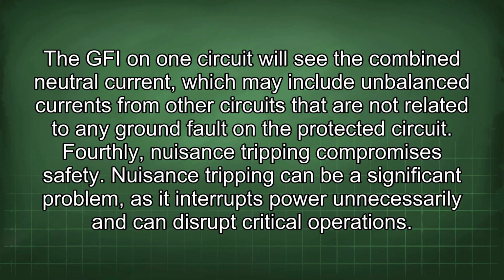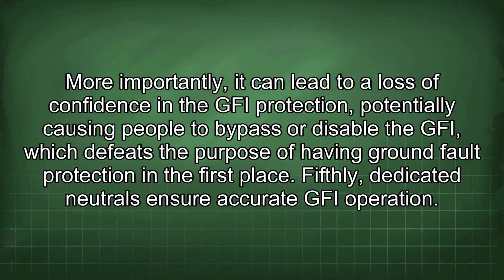Fourthly, nuisance tripping compromises safety. Nuisance tripping can be a significant problem, as it interrupts power unnecessarily and can disrupt critical operations. More importantly, it can lead to a loss of confidence in the GFI protection, potentially causing people to bypass or disable the GFI, which defeats the purpose of having ground fault protection in the first place.